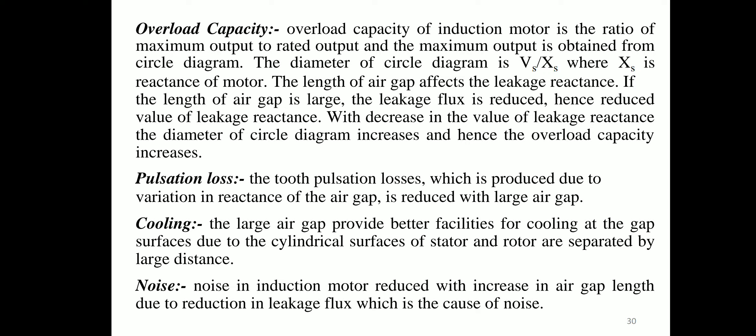The overload capacity of an induction motor is the ratio of maximum output to rated output. The diameter of the circle diagram is Vs / Xs, where Xs is the reactance of the motor. A large air gap reduces leakage flux and hence leakage reactance, increasing the diameter of the circle diagram and thus overload capacity. Tooth pulsation losses due to variation in air gap reactance are also reduced with a large air gap.